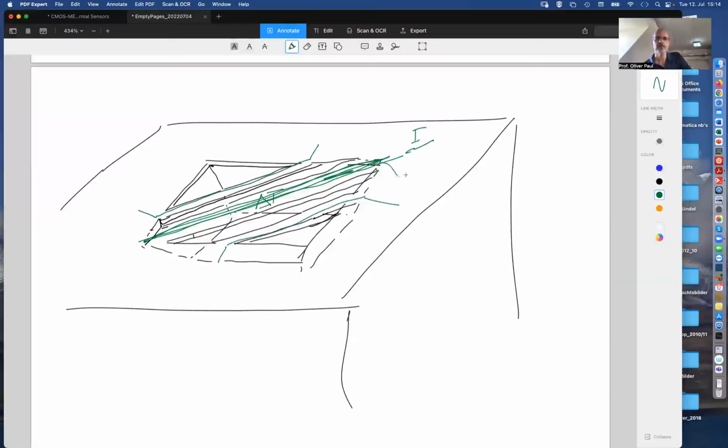With Honeywell, these are made of platinum. And the airstream now goes in this direction. So this beam will receive some heat from the central beam via thermal conduction. It will be heated up to delta T, let's call that left. And then this is delta T right.